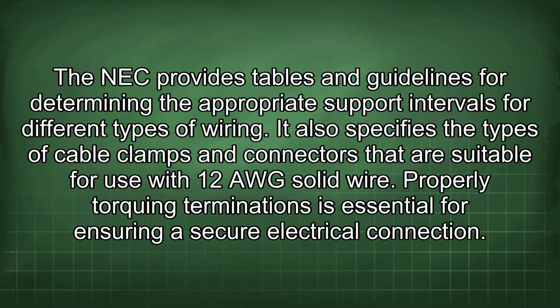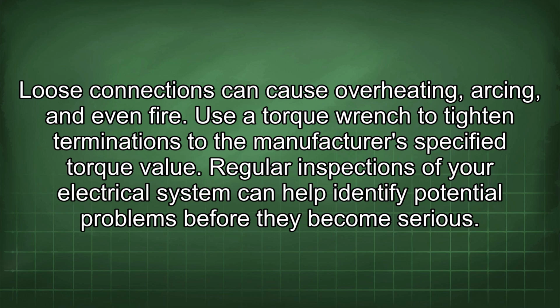The NEC provides tables and guidelines for determining the appropriate support intervals for different types of wiring. It also specifies the types of cable clamps and connectors that are suitable for use with 12 AWG solid wire. Properly torquing terminations is essential for ensuring a secure electrical connection. Loose connections can cause overheating, arcing, and even fire. Use a torque wrench to tighten terminations to the manufacturer's specified torque value.